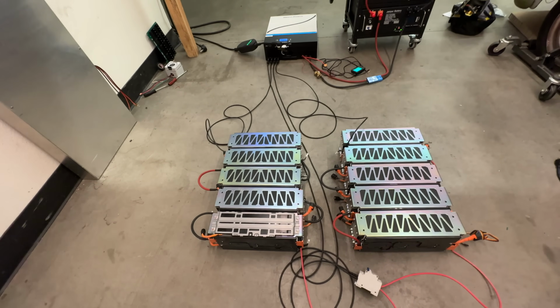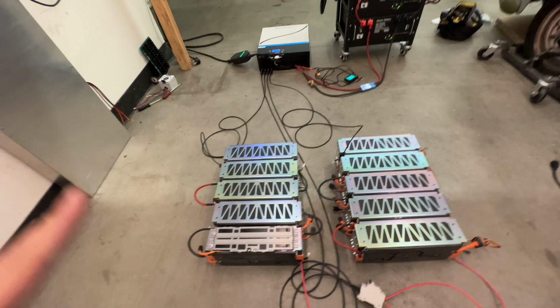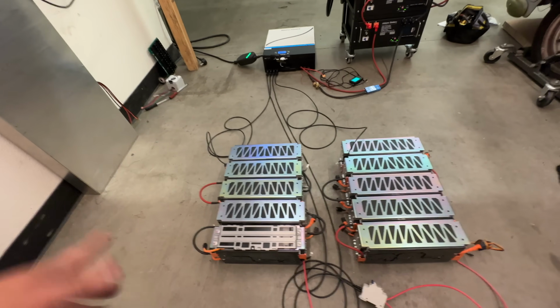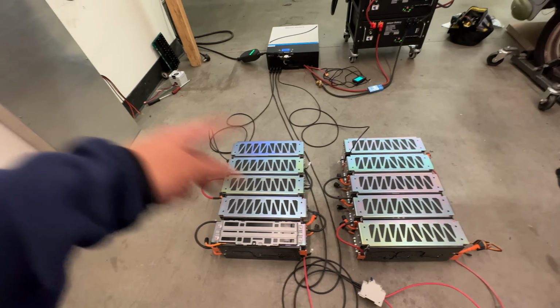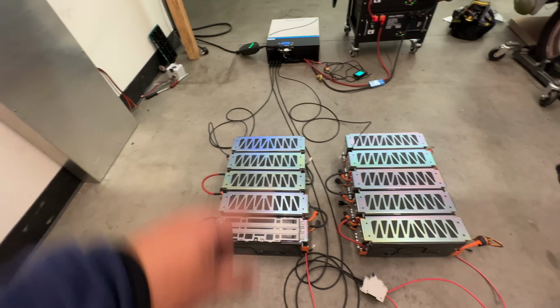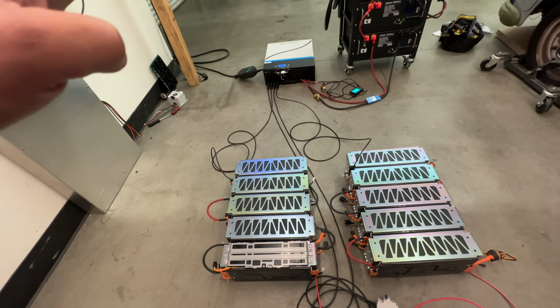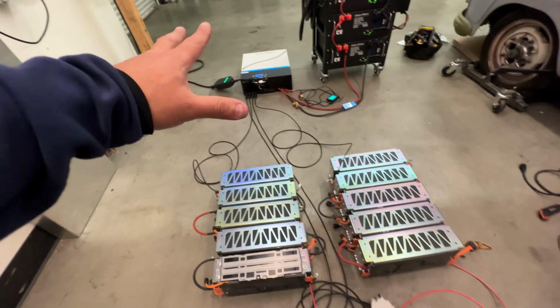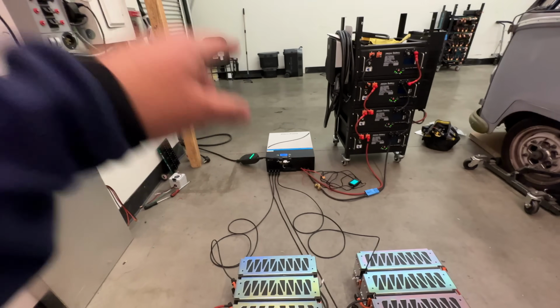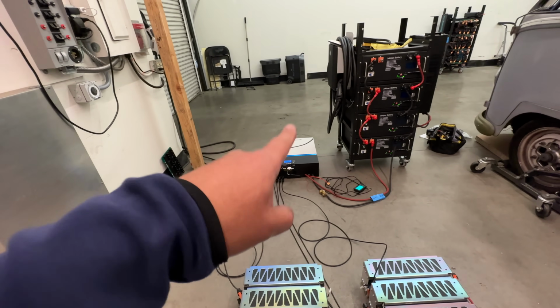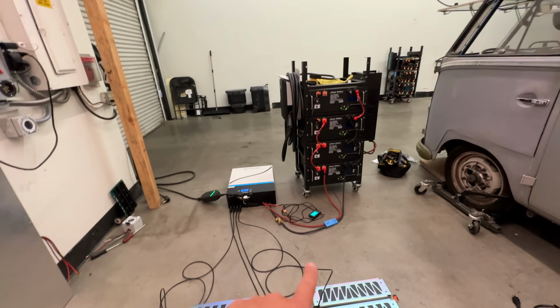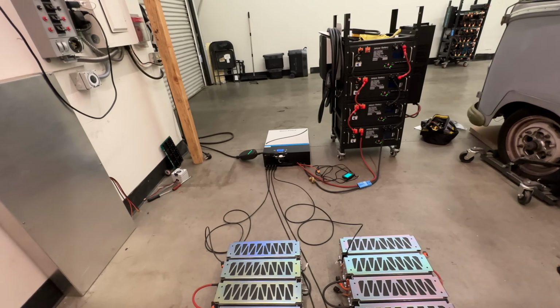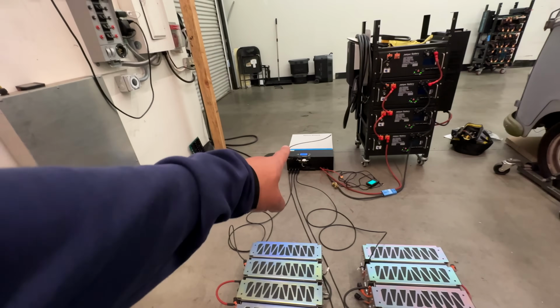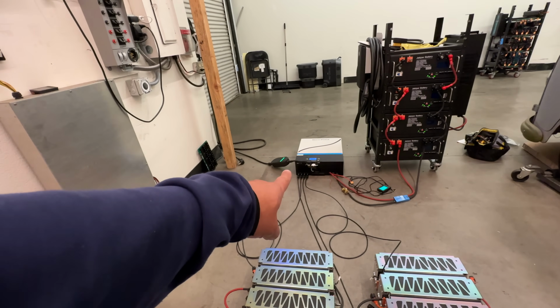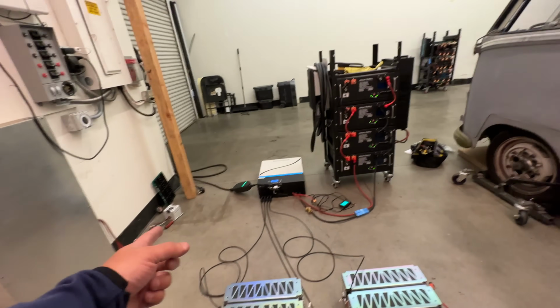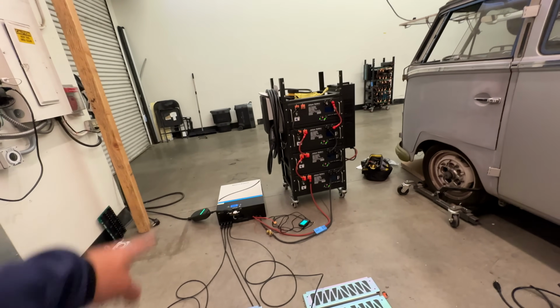And they're 12S. They could put out a ton of power, but I'm not using them for the power right now. I'm just using them for the voltage because they're easy to connect. So I just linked them in series, and they get to about 230 volts, right? So each one of these will put about 230 volts into the inverter there. And so what I've got going, I got this battery connected there because obviously, if you throw 8,000 watts of solar in here, then that inverter needs to put it somewhere. So I have this battery connected in here, and so it is going to try to charge it.